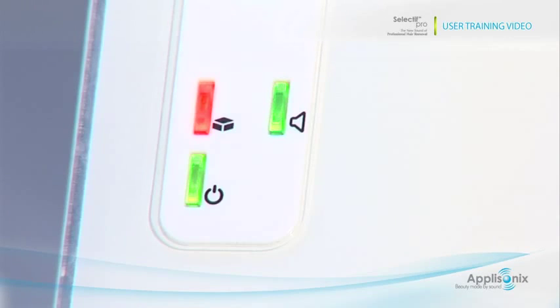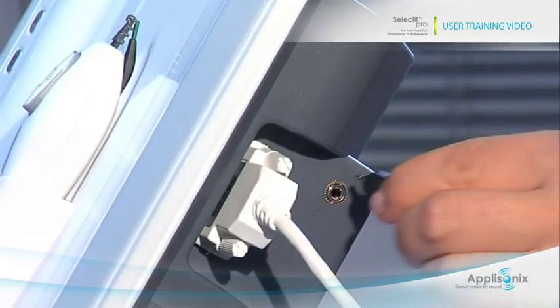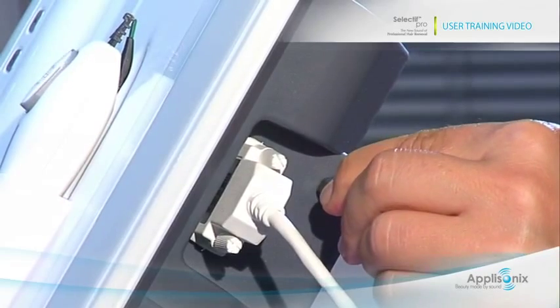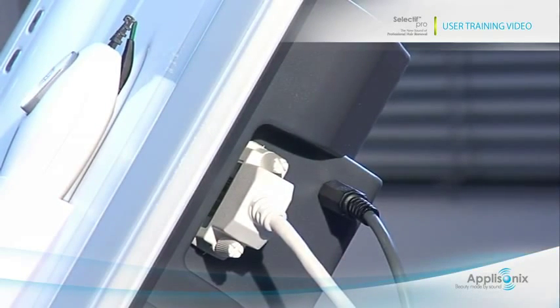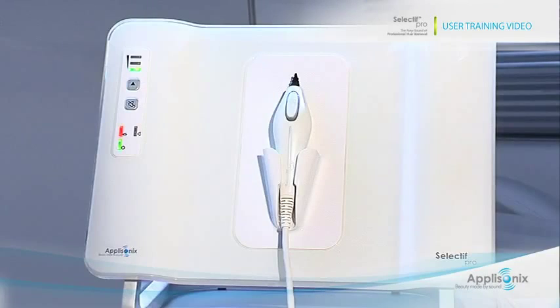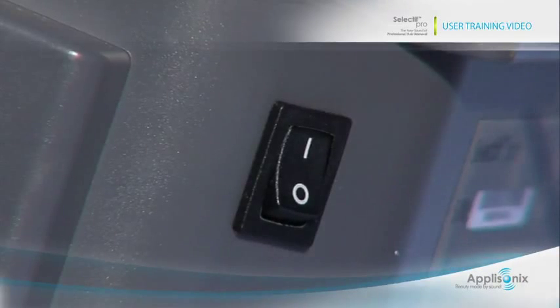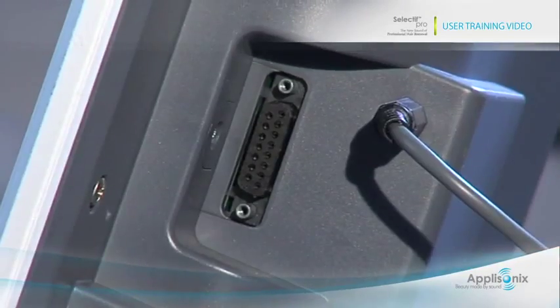When the status light is red, check that the foot pedal is properly connected and that the trigger button on the probe is not pressed. The mode and status indicators on the front panel will provide you with immediate notifications when there is a problem with the system. Let's go over these notifications. When the status light is red and the A mode is blinking, the probe has been disconnected. Turn the system off, reconnect the probe, and continue working.